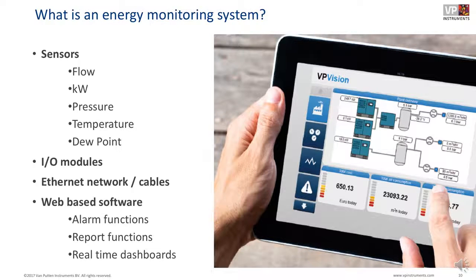A monitoring system consists of sensors. Sensors for flow, kilowatt, pressure, temperature, dew point, or even if you have sensors that have capabilities of measuring particles or oil content. As long as the sensors communicate 4 to 20 milliamp, a Modbus RS485 RTU or Modbus TCP output, then we can connect them to our VPVision monitoring system. To avoid long cable runs, we make use of I/O modules, where we take either an analog 4 to 20 milliamp or a Modbus signal and create a new Modbus TCP connection with the company network. That's how our main data collection system can communicate with sensors that are far out in the field.